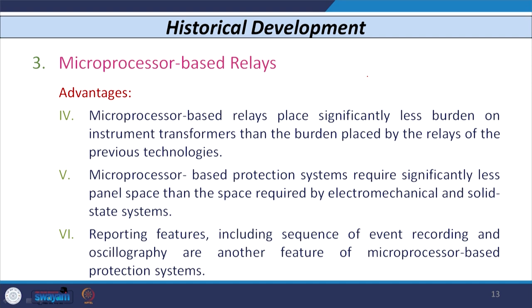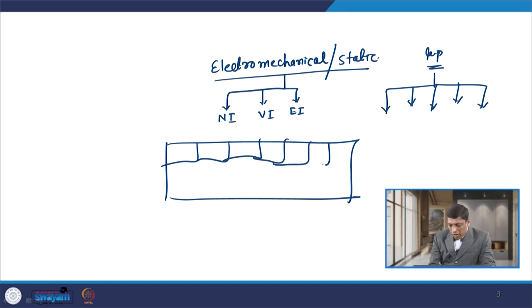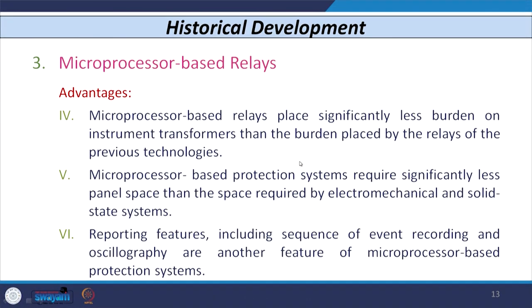Microprocessor-based relays also place less burden — maybe 5 VA or 1 VA — compared to electromechanical or static relays which may have 20 to 30 VA. They also require less panel space, so in a substation with limited space you can accommodate more microprocessor-based relays than electromechanical or static ones. Additionally, they have reporting features: if any event or abnormal condition occurs, it is captured by the relay and you can play back, visualize, or access the data in graphical or text form.